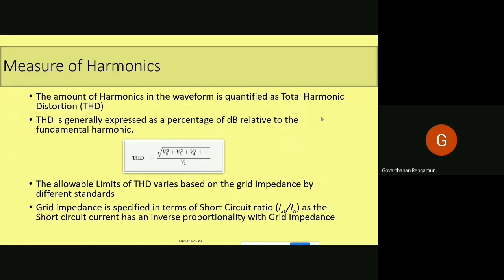The next slide: measure of harmonics. There should be a measure for these harmonics, right? The amount of harmonics in the waveform is quantified as total harmonic distortion. Total harmonic distortion is measured relative to the fundamental frequency. You can see the formula here: the denominator is the fundamental voltage, and the numerator is the square of the different voltages other than the fundamental voltage. So the amount of distortion is quantified as THD, total harmonic distortion.